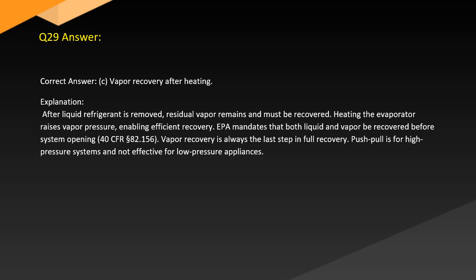Answer. Correct answer: C. Vapor recovery after heating. Explanation. After liquid refrigerant is removed, residual vapor remains and must be recovered. Heating the evaporator raises vapor pressure, enabling efficient recovery. EPA mandates that both liquid and vapor be recovered before system opening, 40 CFR 82.156. Vapor recovery is always the last step in full recovery. Push-pull is for high-pressure systems and not effective for low-pressure appliances.